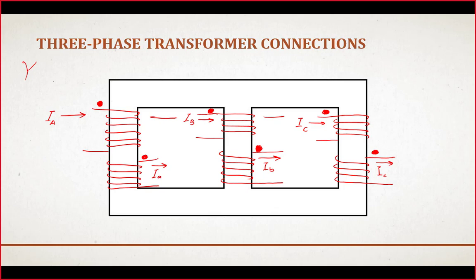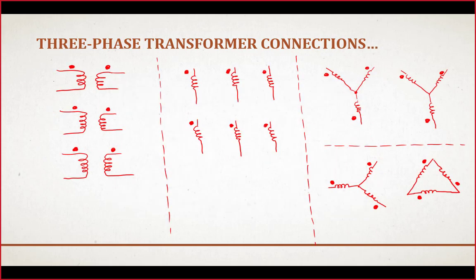Next, we have seen in our previous lecture that in order to draw the delta-Y, Y-Y or delta-delta connection of a three-phase transformer on paper, there are three ways to represent those windings on the high side and low side, because three windings belong to the high side, three windings belong to the low side, and now we want to connect the three windings on one side of a transformer together in Y and delta configuration. So on paper we use these three possible methods.